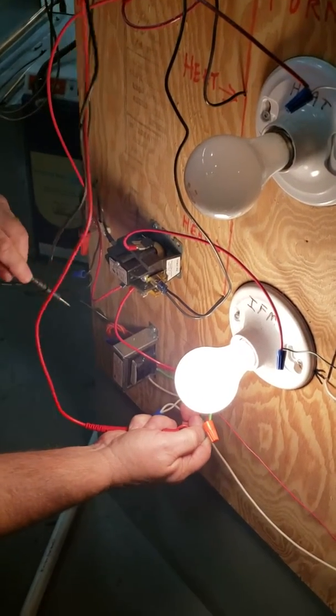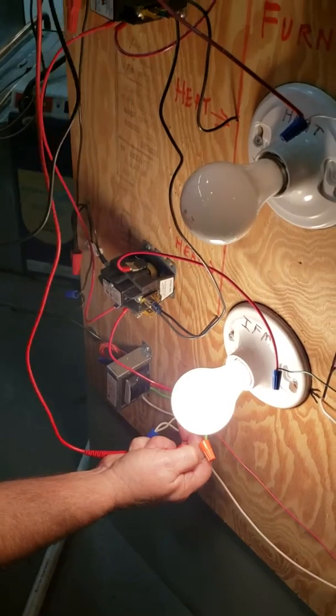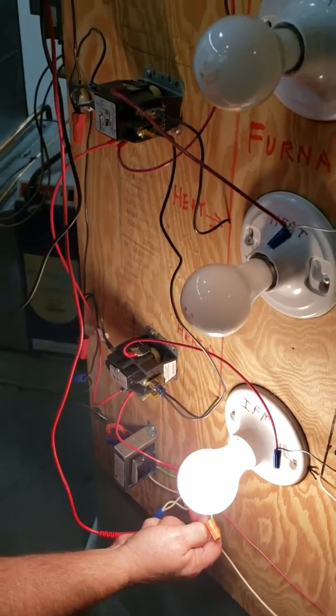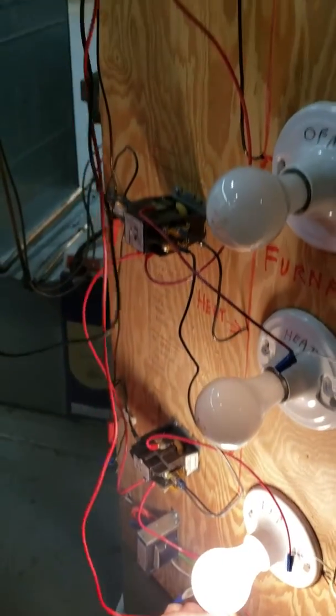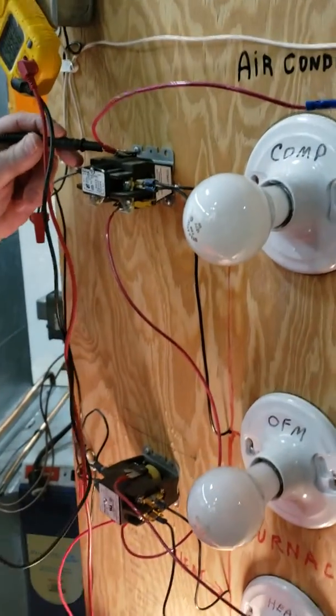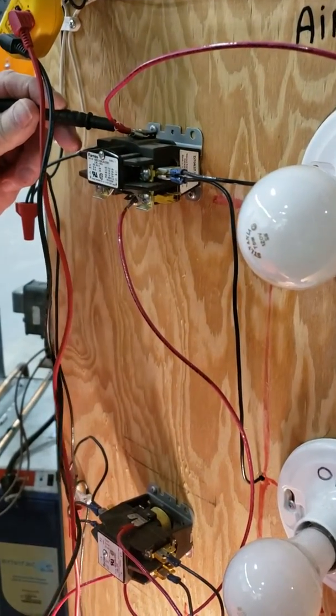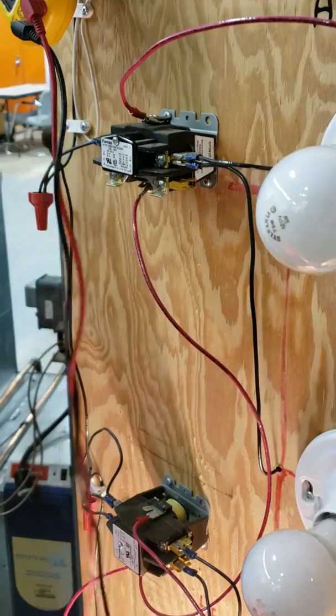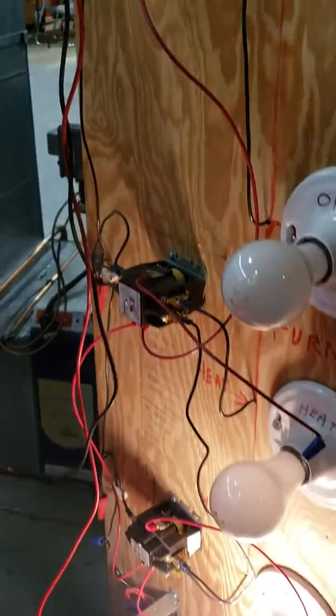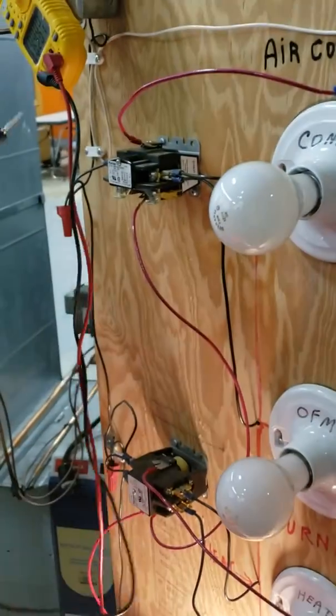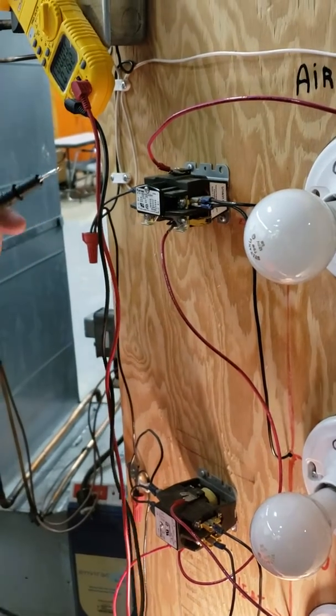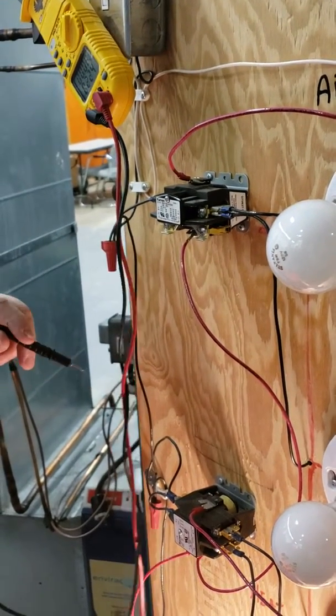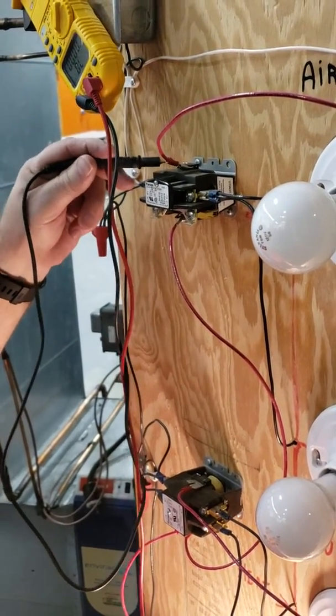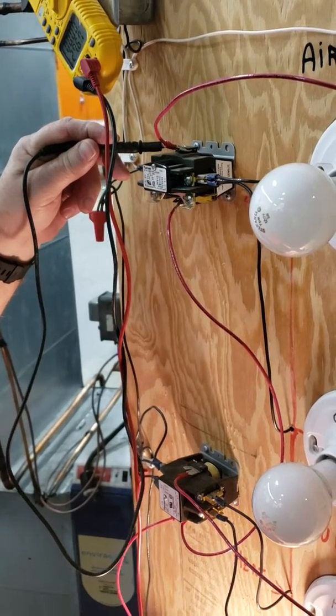Well, I'm getting voltage out of my transformer to my thermostat, which is essentially a switch, right? Yeah. And then it's coming out of that switch, and I'm reading voltage here. So that's telling me I have an open circuit between my output of my transformer. It goes into that thermostat, comes back out of the thermostat. It should be closed. It should be zero. I should not be reading voltage there.